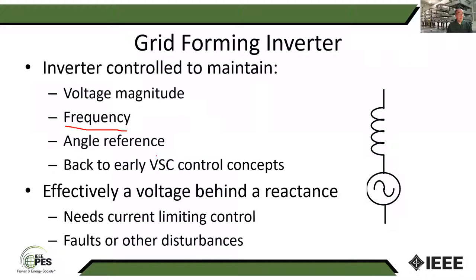And there are some limitations that go with this. This still needs some sort of current limiting control. So if there's a fault on the distribution system or the transmission system this is connected to, it's very important that this is able to limit the current so you don't destroy the power electronic devices in the converter. So there has to be a control loop that's part of this that limits current.